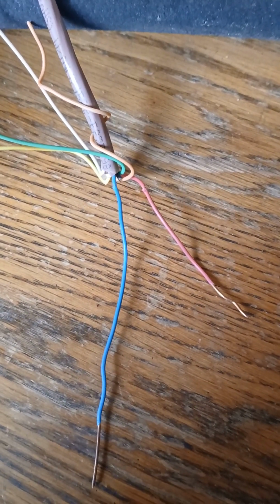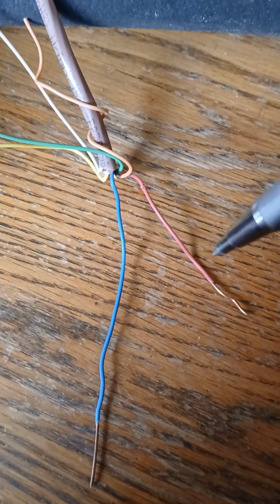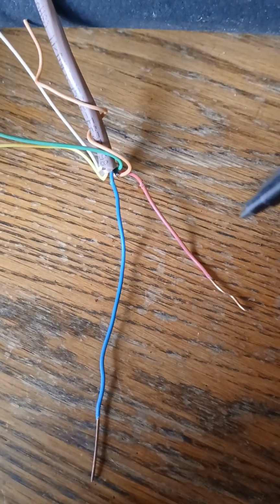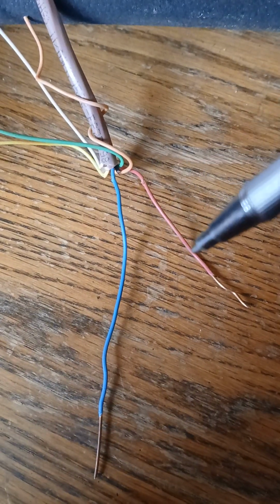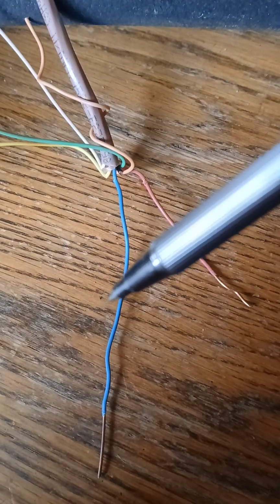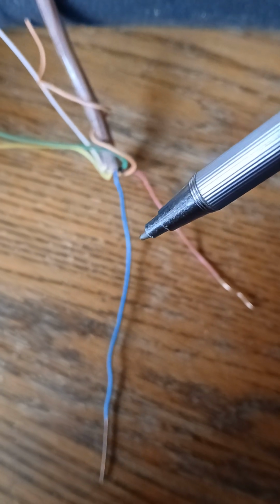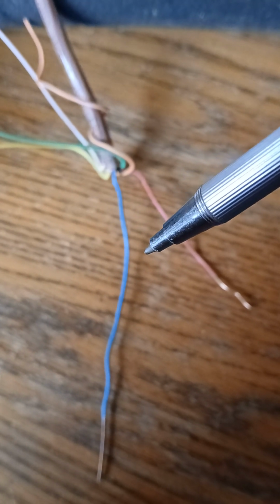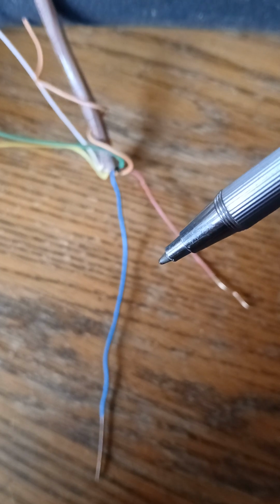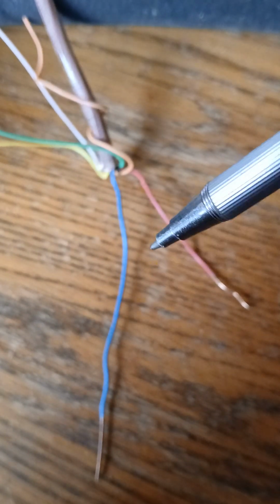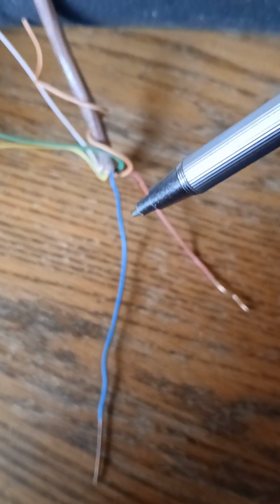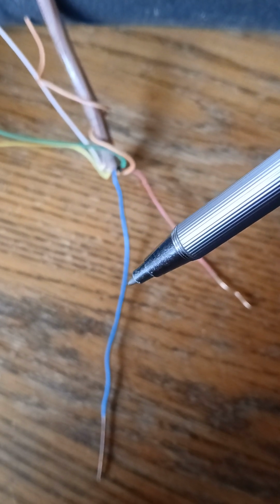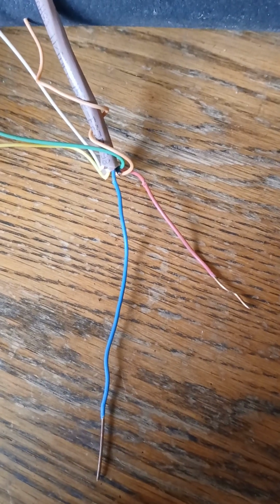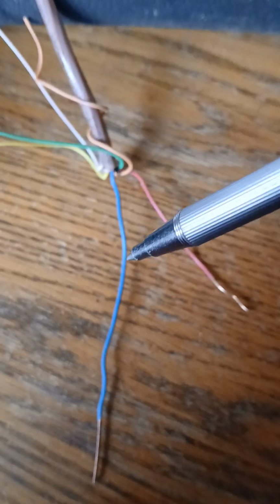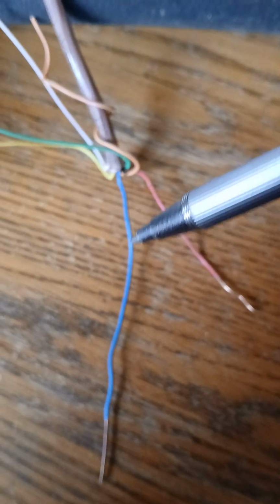So this way, when we see the red wire on the thermostat, we're generally referring to the hot wire. When we see the blue wire on the thermostat, this is residential use, with some commercial applications to be noteworthy here. Normally, the blue wire is the common wire. Do keep in mind, on the blue wire, if you're using a set of batteries, you may not need a common wire. My opinion is it's good practice to use the common wire.